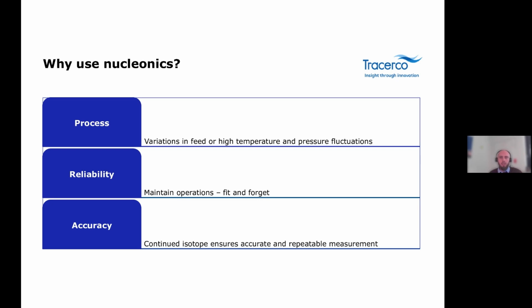Well, these are favoured in some of the more harsh environments or conditions where conventional instruments just don't cut it, or where they can't measure effectively. With the nucleonics, there's an increased accuracy and reliability. The use of gamma isotopes provides a continued output, which means there's no switching off. A few examples of these processes where it's particularly useful include fouling or clogging, erosive and corrosive processes, high process temperatures, or varying pressure and temperature conditions.